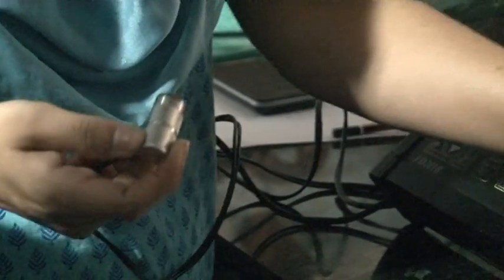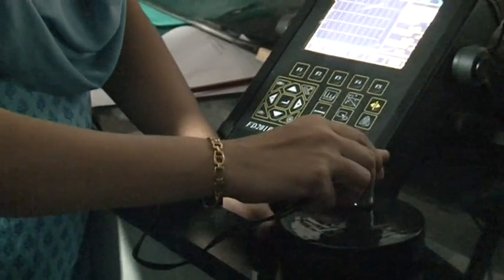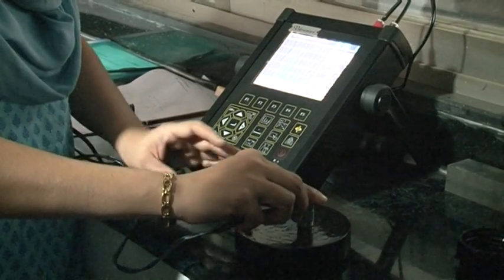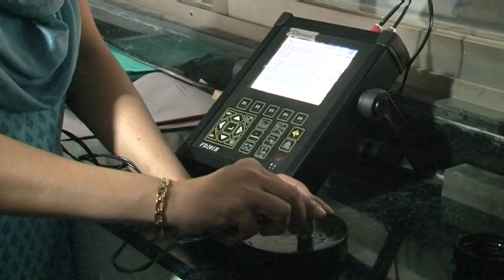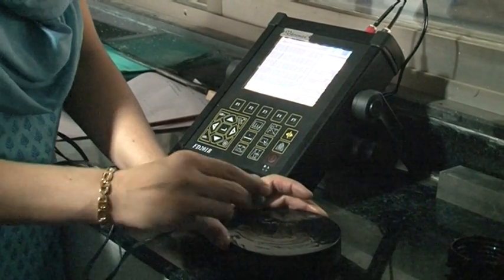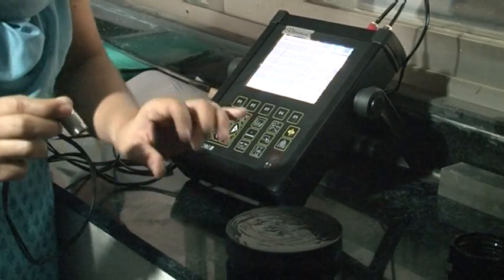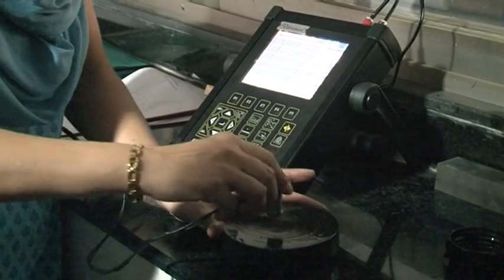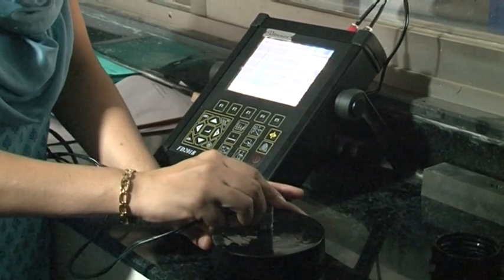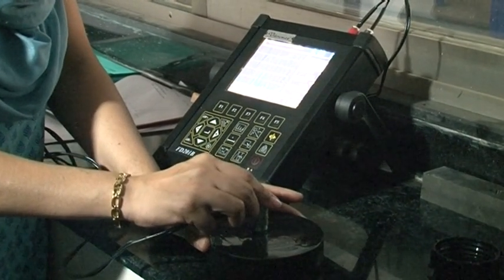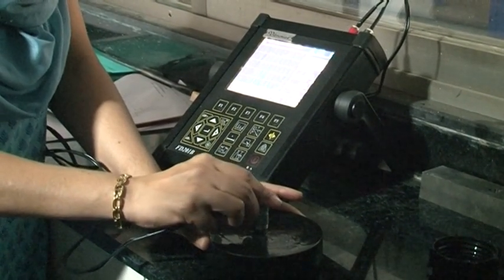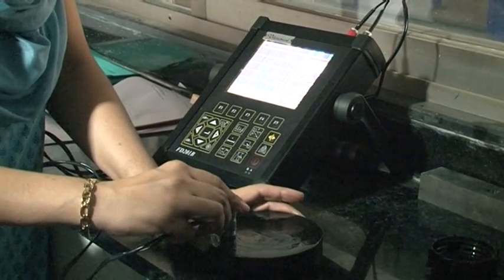If there is any flaw in between, there will be an intermediate peak on the graph. This shows the location of the defect on a linear scale. We can thus make measurements on the XYZ axis and find the exact location to an accuracy of plus minus 5 mm. A test piece up to 6000 mm length can be checked.